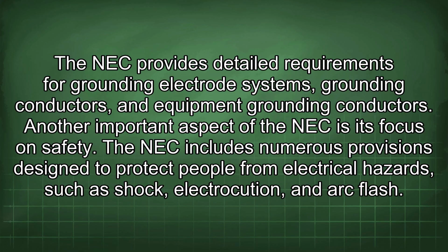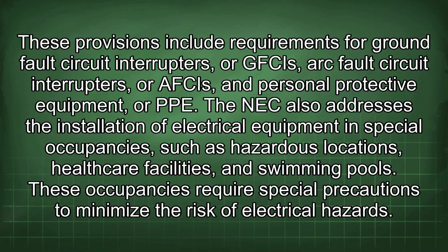Another important aspect of the NEC is its focus on safety. The NEC includes numerous provisions designed to protect people from electrical hazards such as shock, electrocution, and arc flash. These provisions include requirements for ground fault circuit interrupters, or GFCIs, arc fault circuit interrupters, and personal protective equipment, or PPE. The NEC also addresses the installation of electrical equipment in special occupancies, such as hazardous locations, healthcare facilities, and swimming pools. These occupancies require special precautions to minimize the risk of electrical hazards.